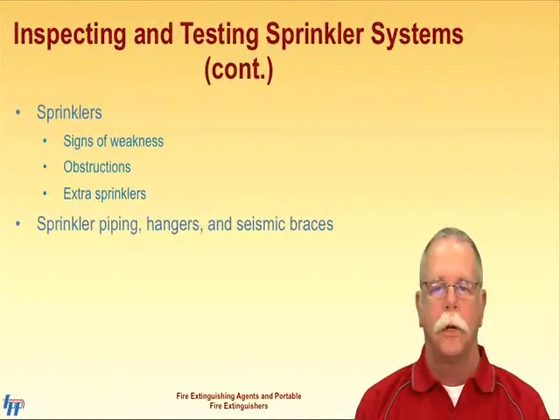When inspecting sprinklers, two of the most common problems facing the fire department are obstructions and improperly spaced heads due to remodeling or moving equipment and commodities. Obstructions include materials that alter or block the discharge of water from the heads, or block access to the riser or FDC.